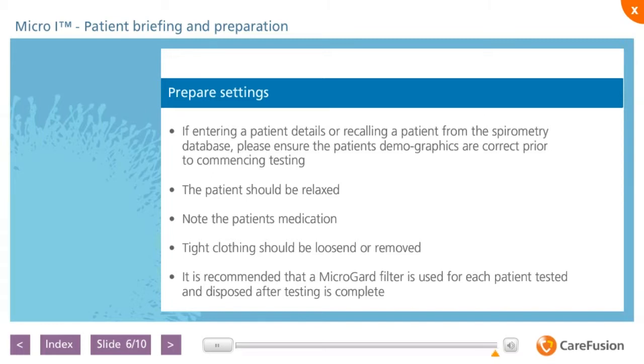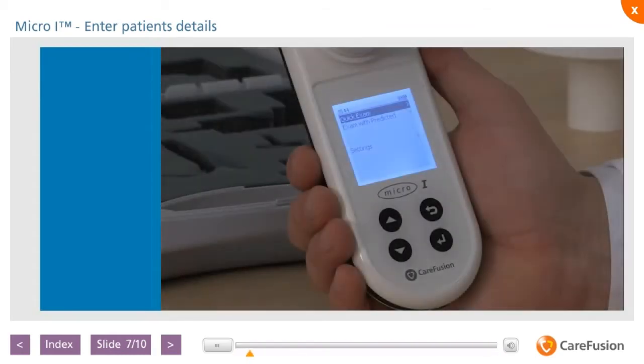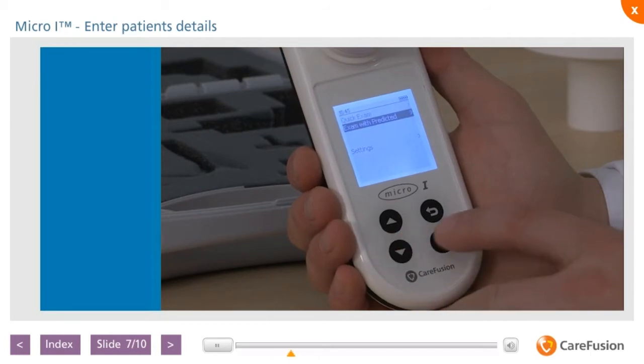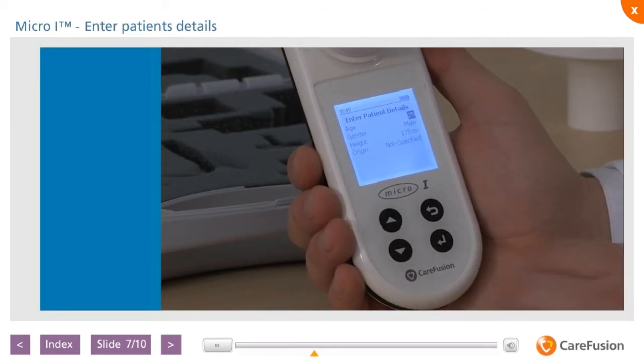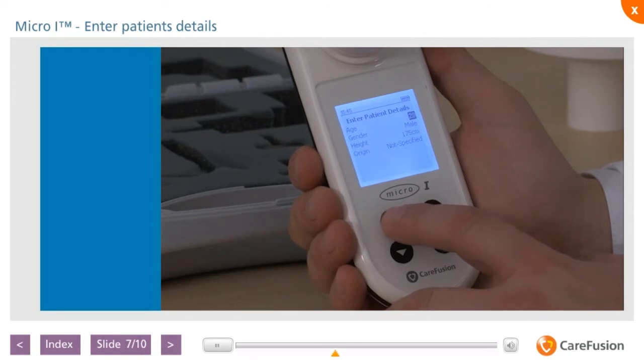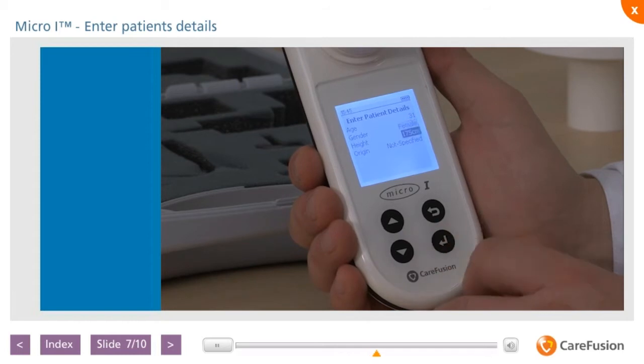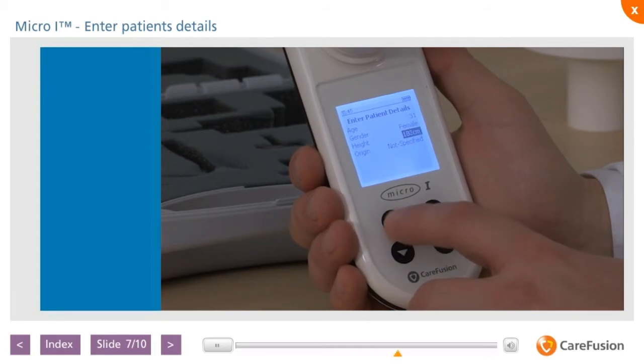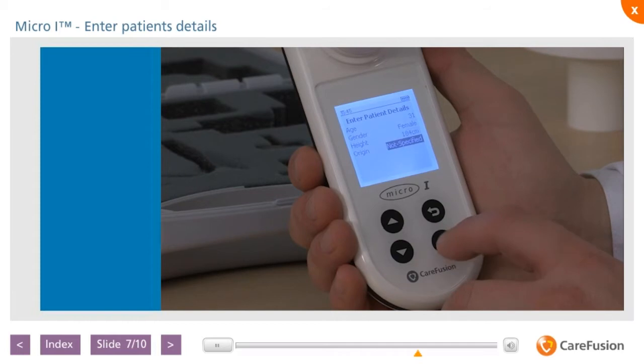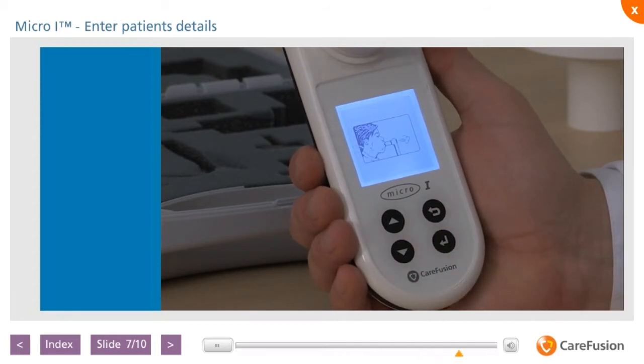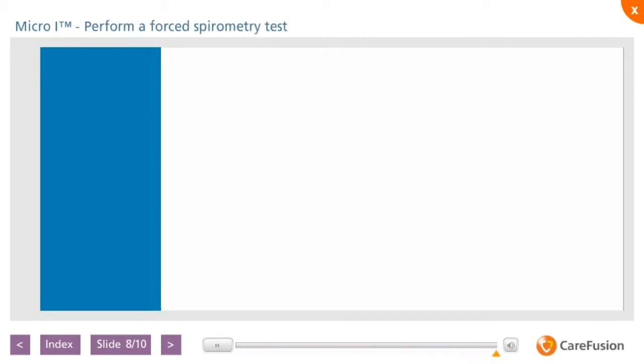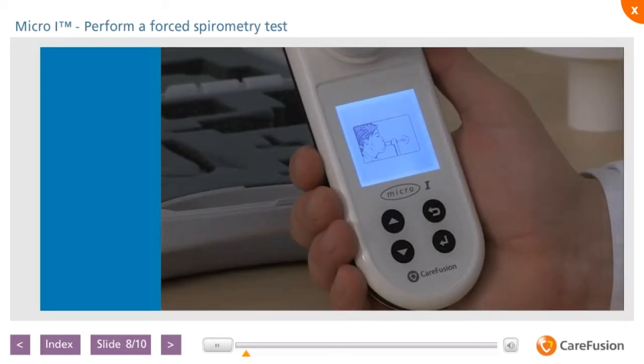The Micro I spirometer main menu enables tests to be performed for quick examinations without predicted values or with predicted values. To obtain predicted values, the patient's age, gender, height and origin need to be entered. Use the up and down arrow keys to change the default and then press Enter. Once complete, the patient's blow legend is displayed in preparation for a test. The Micro I will display the blow legend.